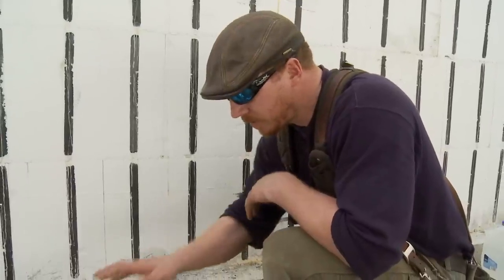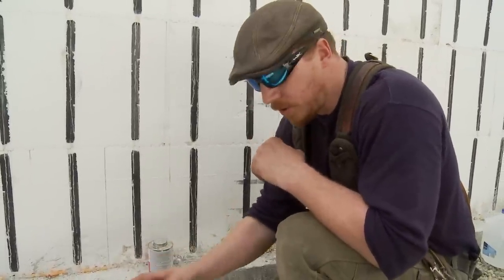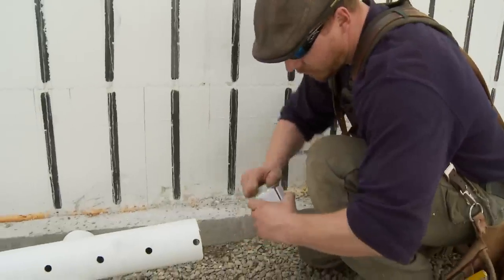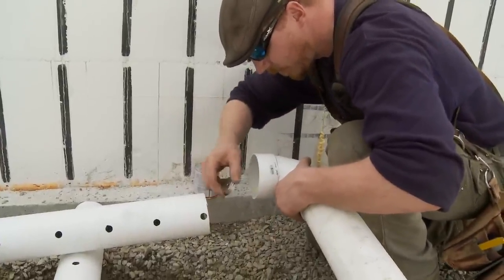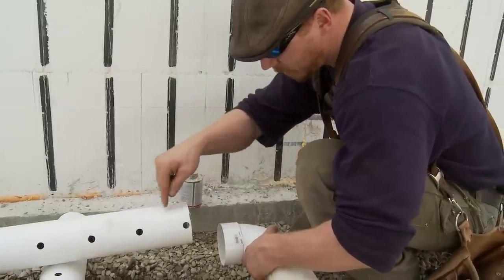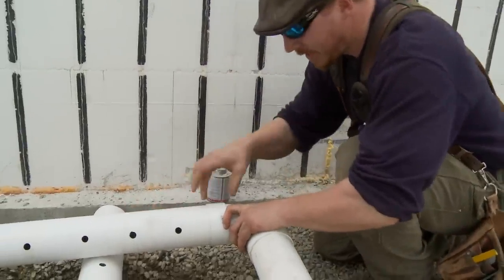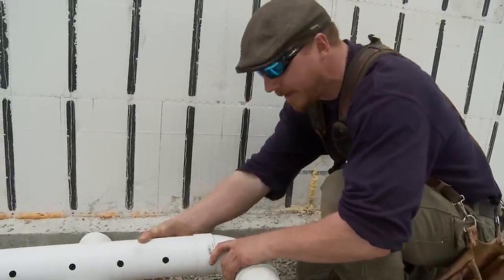In Fairbanks, what's available is high-density polyethylene pipe, also known as HDPE. The issue with HDPE pipe is you cannot use typical plumbing glues for PVC on this type of pipe. It does however work because you're still using a PVC fitting — the PVC glue will soften the fitting, and when you put it on this HDPE pipe you can see there are many mild ridges on the outside. If you use plenty of glue and squeeze the two together, that glue hardens up inside all these ridges and creates a secure enough mechanical bond that you have pretty good assurance this pipe isn't going to come apart once it's installed in the ground.